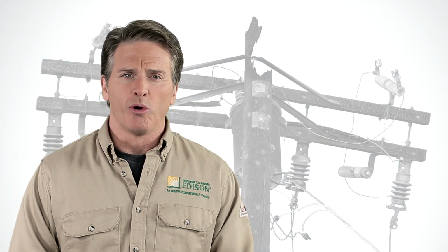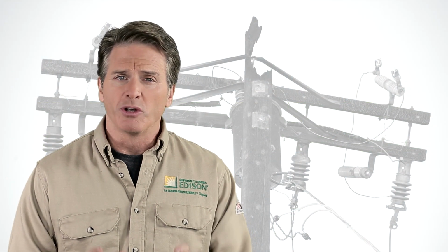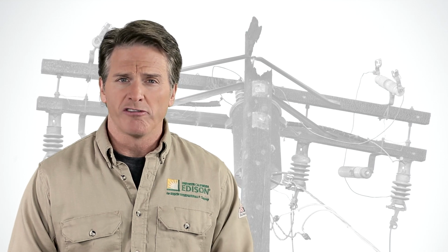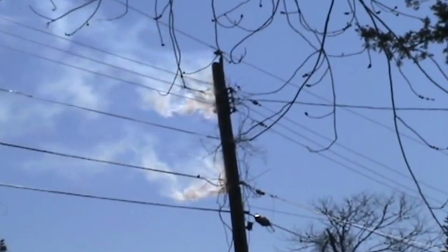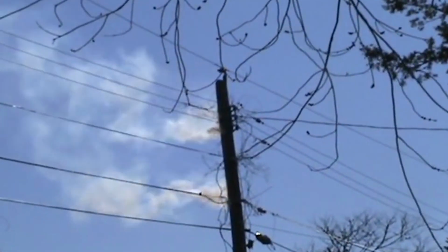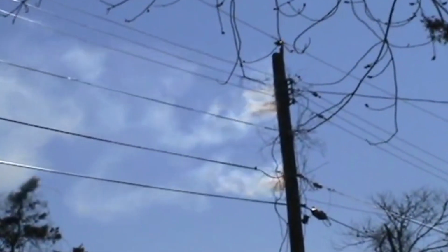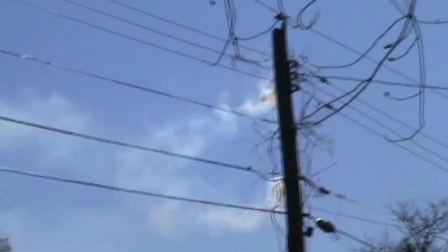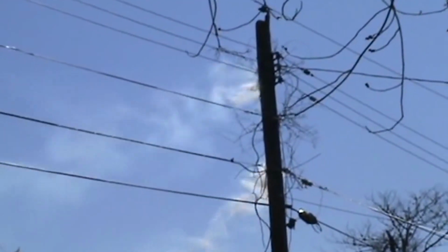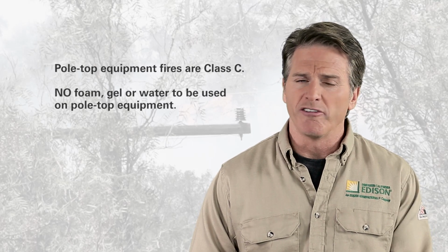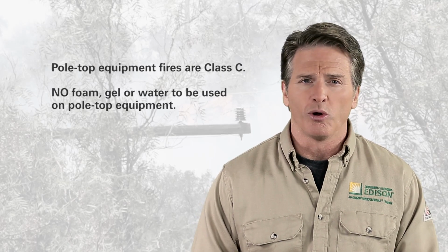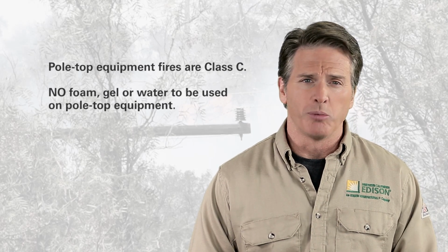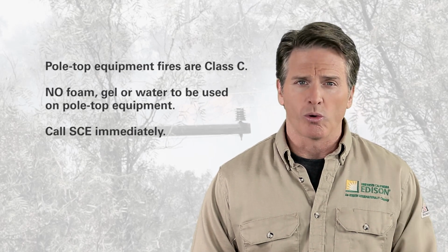Your first task on a pole fire is to identify the problem, because your plan of action depends on what is on fire and where the fire is on the pole. Most fires at the top of the pole are pole top equipment fires involving a transformer, capacitor, insulator, switch, automatic switch, or other apparatus attached to the pole. Consider these energized electrical fires as Class C. Do not spray foam, gel, or water on any pole top equipment or fires at the top of the pole. Notify us and wait for our qualified utility workers to arrive.